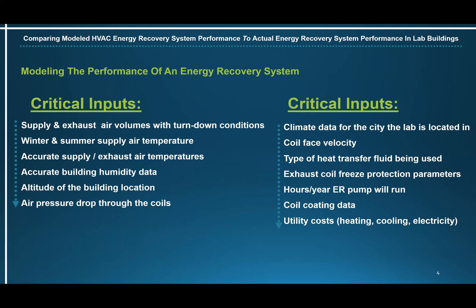Exhaust coil freeze protection parameters — let me take a minute to explain this one. To protect the exhaust coils from freezing, some of the warm heat transfer fluid going to the supply coils needs to be bypassed to the exhaust coils to ensure that the fluid going into the exhaust coils is warm enough to prevent freezing. The fluid being bypassed to the exhaust coils never gets to the supply coils, so it's not available for energy recovery. This amount of fluid needs to be calculated and accounted for in the model. If it isn't, the performance of the energy recovery system will be falsely elevated.